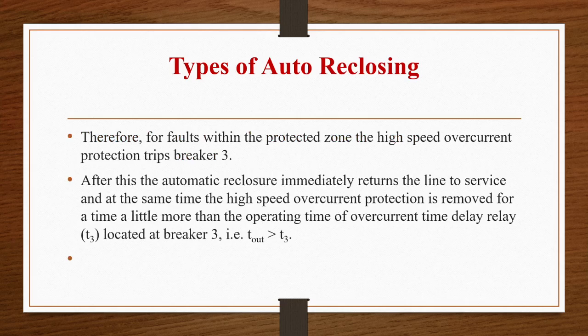Therefore, for faults within the protected zone, high speed overcurrent protection trips breaker 3. So whenever there is a high speed overcurrent, circuit breaker 3 will be tripping. After this, the automatic reclosure immediately returns the line to service, and at the same time the high speed overcurrent protection is removed for a time a little more than the operating time of overcurrent time relay T3, which is located at circuit breaker 3.